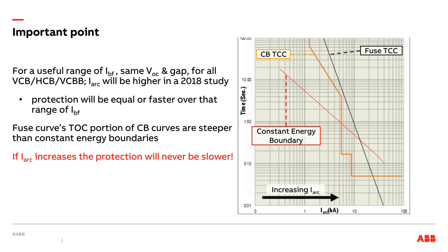If you still have multiple exposure modes where power could be coming from in the same enclosure, now you need to look at the fact that horizontal, vertical, all else being the same, affects both incident energy and arcing current. So for example, if I have VCB and VCBB, you probably need to look at both, because the VCBB will give you much lower arcing current, which means, again, you could be in the region where your protection on that breaker goes from instantaneous to that slow portion up high in the curve. And yeah, VCB per unit time is less energy, but your time is just multiplied by a factor of 10.